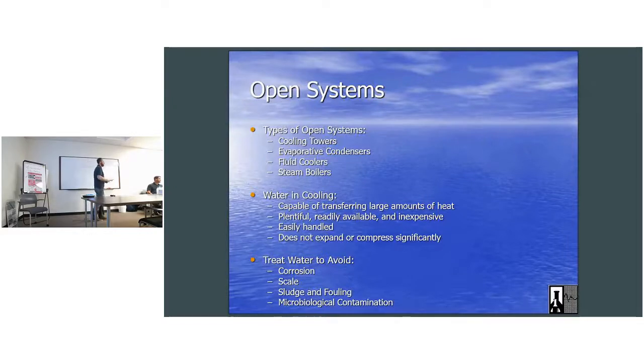Roughly to keep in mind, while you're at the hall, Kurt, they've got 2 pumps that used to be on a chiller. One of the pumps they ran constantly. The other one, and this was pulled out of some location, sat idle. And the intake screen is just trash. But the one that was running is in good shape. Those should be flip-flopped. They should run lead lag. They weren't running lead lag. So they use that as an example. It's over by the chiller, the screw chiller stuff.